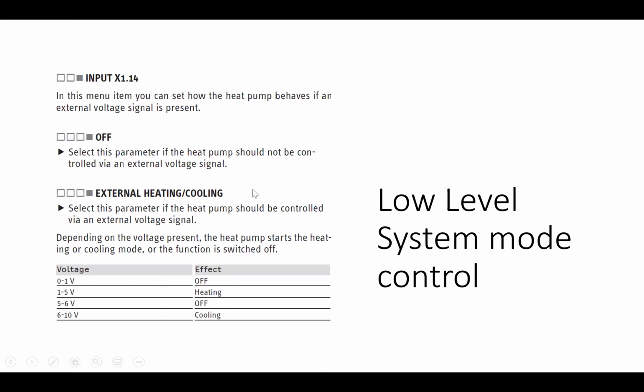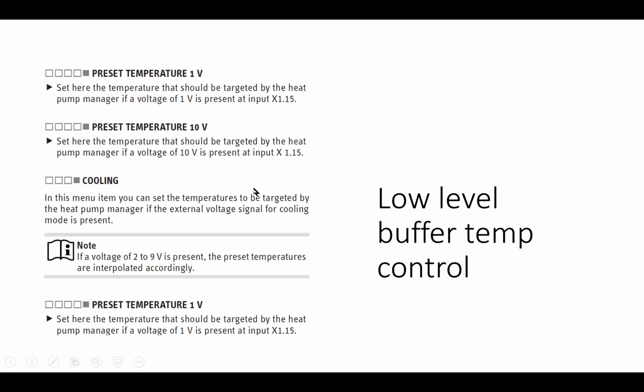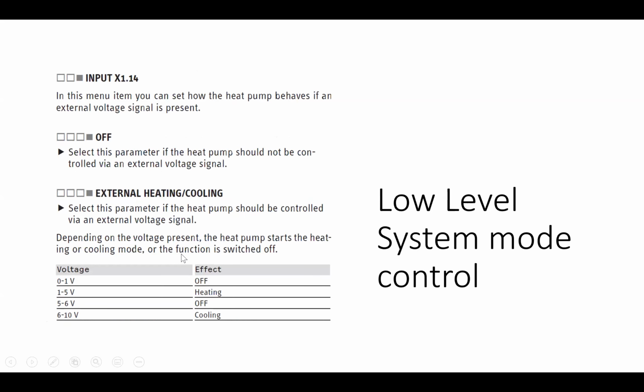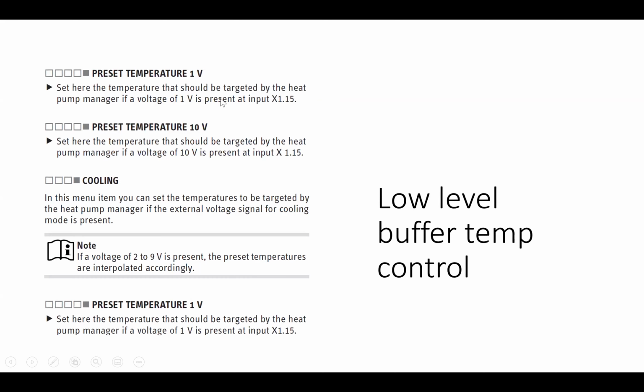Okay, very simple. Then we can look at X115. So X115 being the second 0 to 10 volt terminals that I was showing you. X115, we also can give it a 0 to 10 volt input. What we do is we set a buffer temperature at the 10 volt point, and we set a buffer temperature at the 1 volt point. And then when your controller is giving it a 0 to 10 volt variation, it's incrementally changing the buffer temperature set point. So we can choose a mode via low level control, and we can choose what temperature the set point in the buffer tank is via a 0 to 10 volt control.